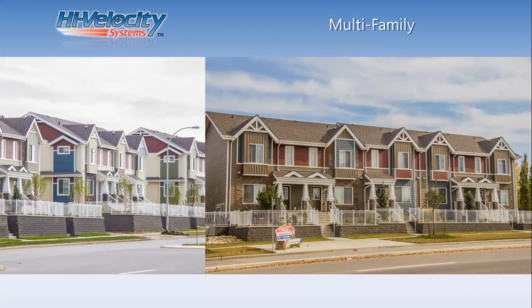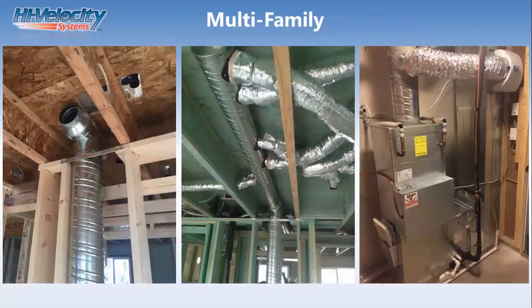Sure, you can just throw money at these jobs and have the right solution, but having a cost effective solution is another thing, which we have been able to provide with our high velocity package, our low temperature heat pump, and most often an electric backup heater for electric only projects, or a gas hot water heater as the hydronic backup solution. In these type of facilities with our smaller duct, we can get the installation to be almost cookie cutter, where guys are installing 7 plexes in 2 days because of how simple and easy the ducting solution becomes on these sites.